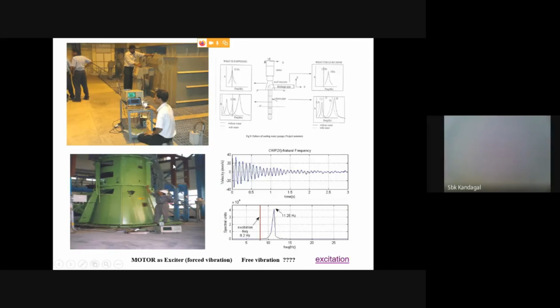Okay, fine. So now let us go to one of the important applications in the power plant, where you have condition health monitoring, rotary systems, etc. You can look at one of the power plants in India, wherein this spool structure has all the accessories to drive this column pipe, which will in turn send water to the generator for cooling. It is driven by a motor on the top, and this trapezoidal thing is the portion above the ground.